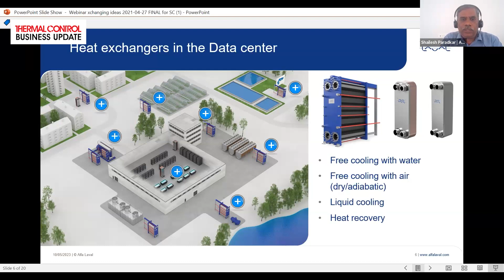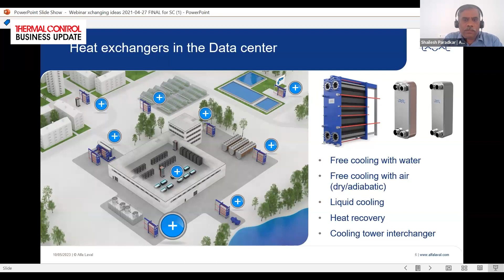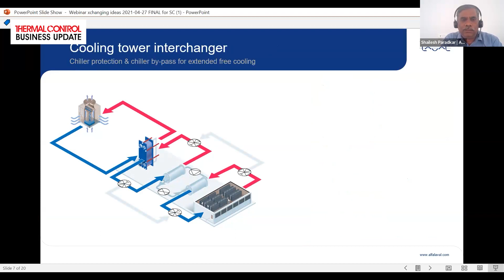And one of the important sustainability drives Alfa Laval is promoting is a cooling tower interchanger. All chillers will have shell and tube heat exchangers, and due to the constructional nature of shell and tubes, many times you see fouling of the tubes. Fouling of the tubes creates resistance to the heat transfer. So as the fouling increases, you have higher and higher discharge pressures, and as your discharge pressure increases, you have more and more electricity consumption in your chillers. So what Alfa Laval proposes is the cooling tower interchanger, where a plate heat exchanger is placed in between the shell and tube condenser and the cooling tower. This actually separates the circuits, and it acts as fouling protection.